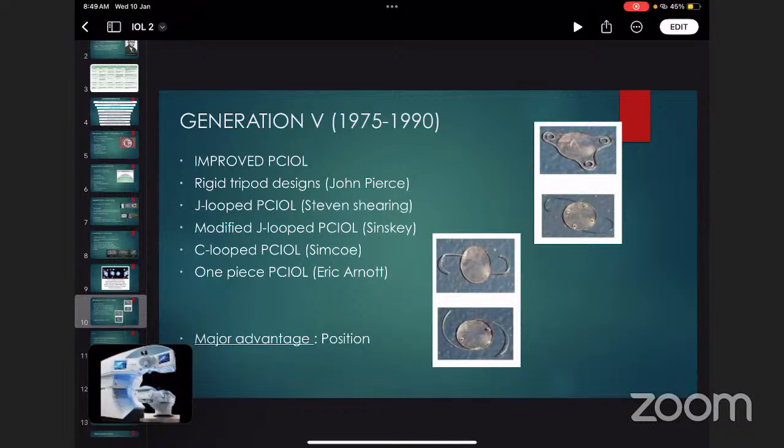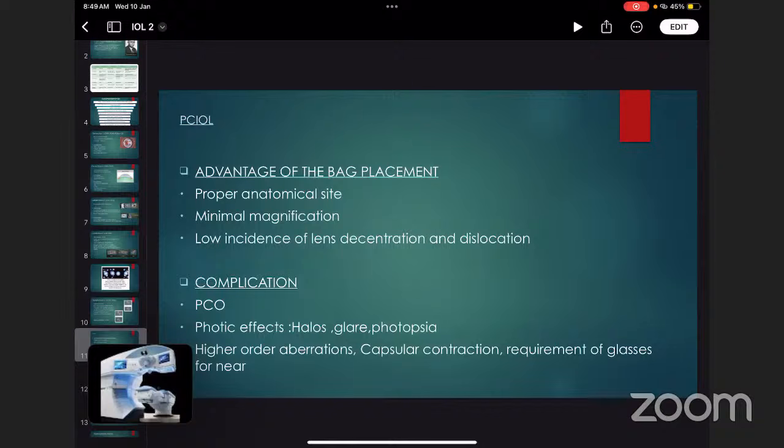Generation 5, from 1975 to 1990, was improved posterior chamber IOL with designs like rigid tripod design, J-loop PC IOL, modified J-loop PC IOL, C-loop PC IOL, and One Piece PC IOL. The major advantage was the position. As it was placed in the back, advantages were proper anatomical site, minimal magnification, low incidence of lens decentration and dislocation. Still, complications included posterior capsule opacification, photic effects such as halos, glare, photopsia, higher order aberrations, capsular contraction, and requirement of glasses for near.